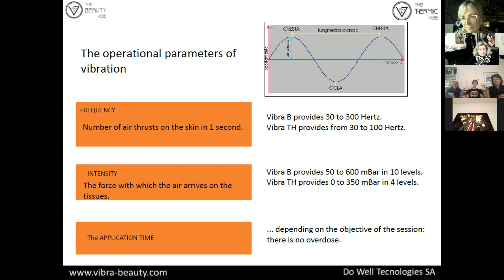Intensity is the force with which the air arrives on the tissues. This force is not very strong, because the vibration is not hard, not like other devices that use many times more pressure force. We provide from 50 to 600 millibar in 10 levels, and you can try. We suggest a medium level, and if a person has a lot of fat or a lot of water in the body, you know that fat and water can absorb vibration, so it's suggested to use more intensity. For the application time, we have our book of protocols, where we made a standard time of about 40-45 minutes, and that is the suggestion we made.